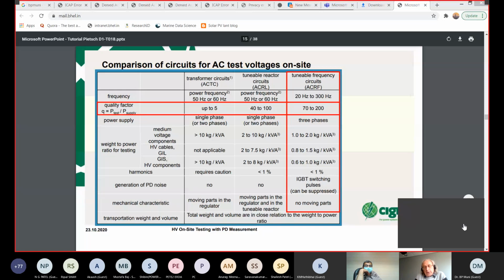Why? Because this produces a very big and steep impulse, du over dt, or a current change in a very steep range, meaning microseconds. Due to the speed of the wave on the cable, about 150 meters per microsecond, if you have a time resolution of a little better than one microsecond, half a microsecond, you can pinpoint to several tens of meters at most, if the cable is very long. If the cable is shorter than one kilometer, you can pinpoint to several meters.